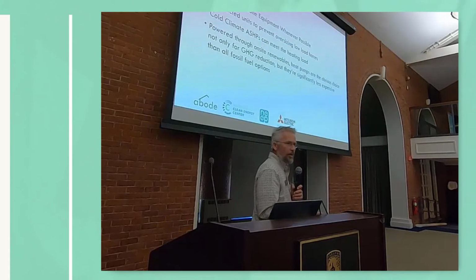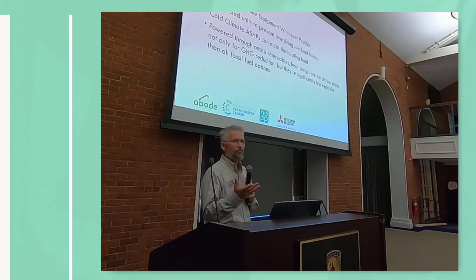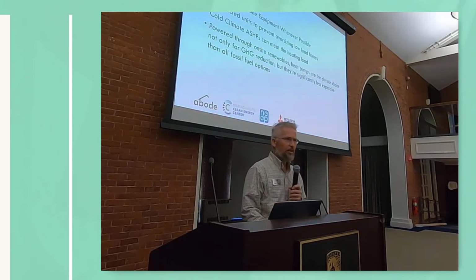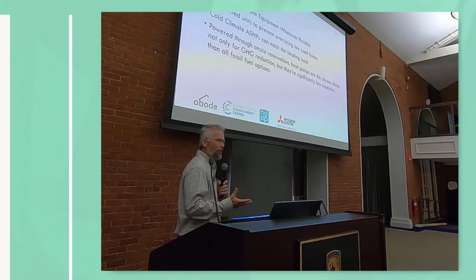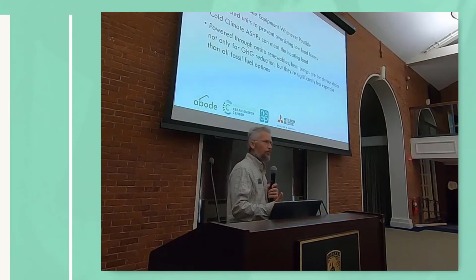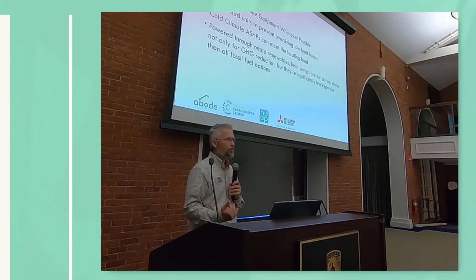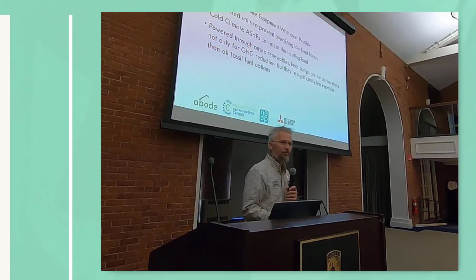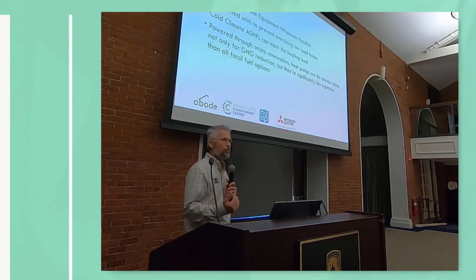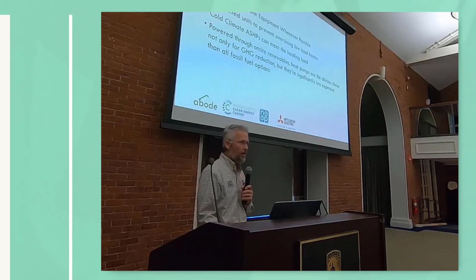I can tell you that, and I managed the rebate program in Maine for 7 years. We have 40, 50,000 homes with heat pumps in them, and there's no evidence that there's any increase in the incidence of frozen pipes. So I'm not sure that I can understand the conservative nature and the caution, but the consequence of having heat pumps in Massachusetts switch over at 35 degrees or 40 degrees is that you're only going to be covering a tiny fraction of the heating season. You're only going to reduce maybe 20% of your carbon emissions by having that high of a turnover temperature.